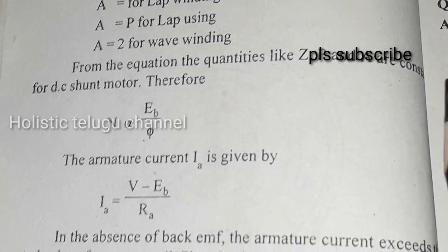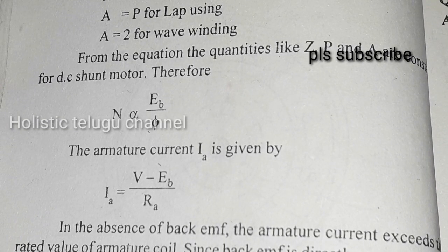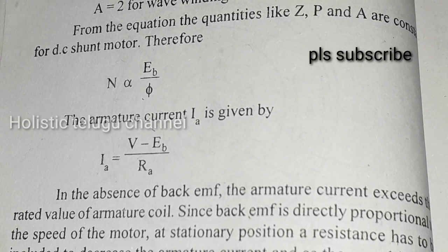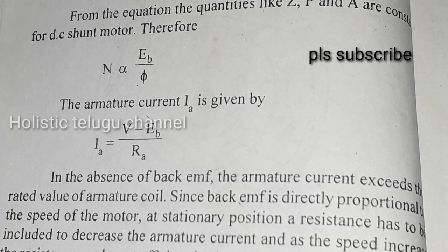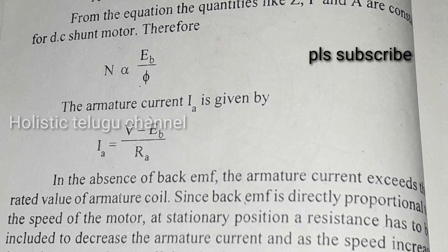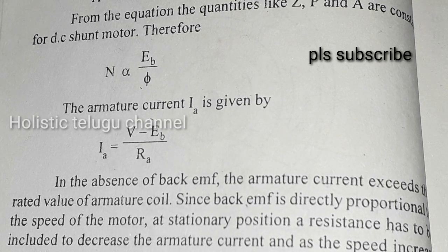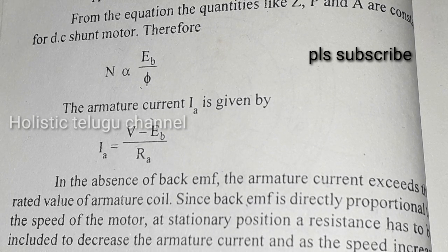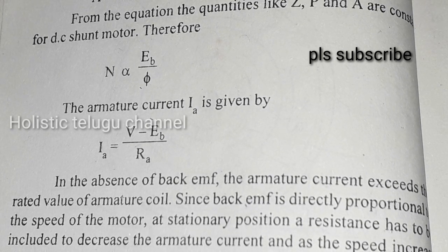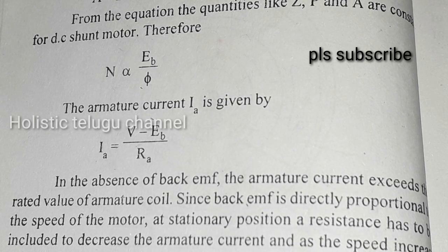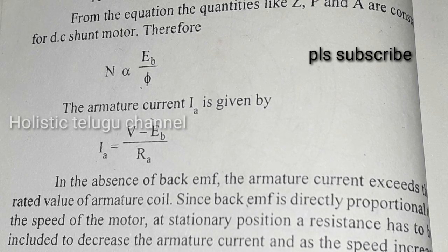The armature current IA equals V minus EB divided by RA. In the absence of back EMF, armature current would exceed the rated value. Since back EMF is directly proportional to speed, at stationary position a resistance must be included to limit armature current. As speed increases, the resistance can be cut off since back EMF regulates the magnitude of armature current.